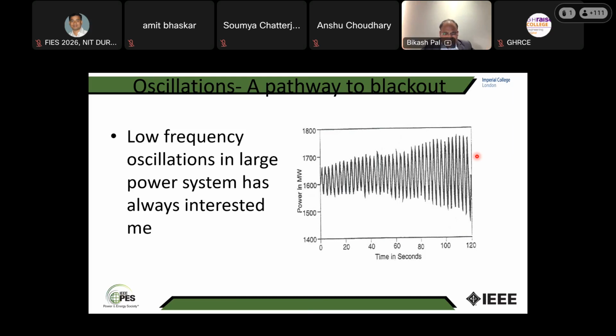So imagine the transmission circuit as a spring, the inductance as a spring. And the mass on the two ends, imagine them as a big mass: the rotor, turbine, generators, all mass. So it's a dynamic equilibrium at 50 Hertz. Now on that, if there is a sudden change in the power flow, that mass and spring start oscillating. Like if you have a pendulum with a mass, you just push the pendulum a little bit, touch it, and then you see that it is actually oscillating like that. So this is the oscillation.